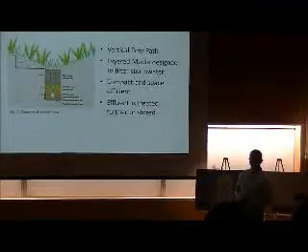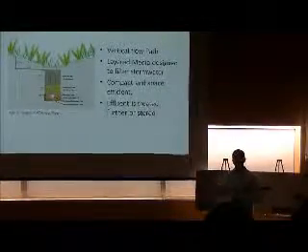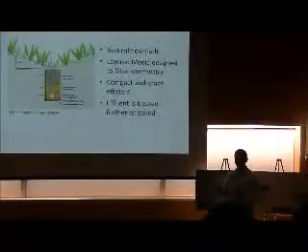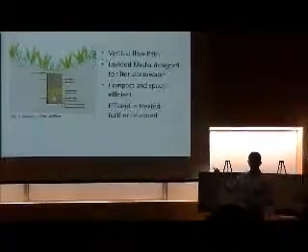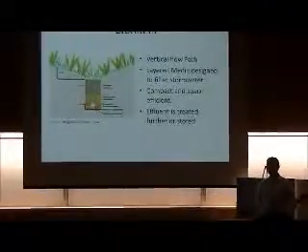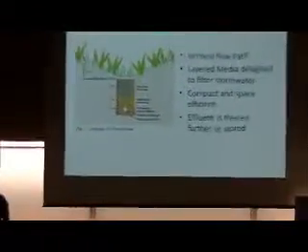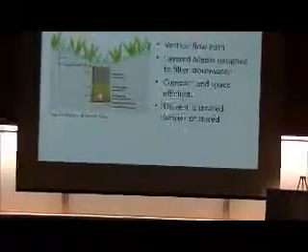Looking at biofilters, they filter water vertically through a set of layered filter media, each is specifically designed to filter out pollutants. Because of this, they are much more compact and space efficient, and they can be pretty much anywhere. The effluent or the output of the biofilters is poured into a perforated pipe where it can be further treated or stored in an underground basin.